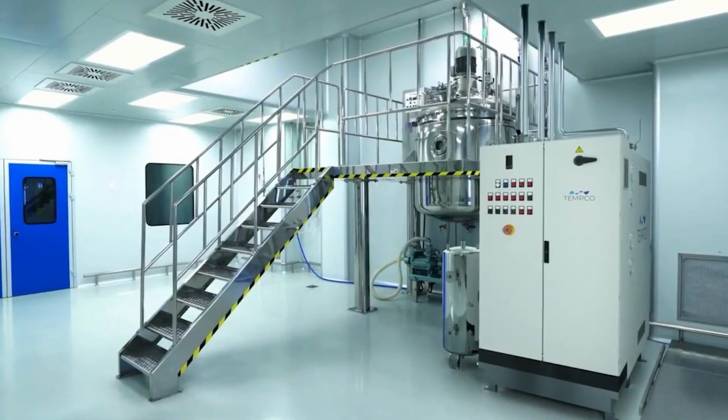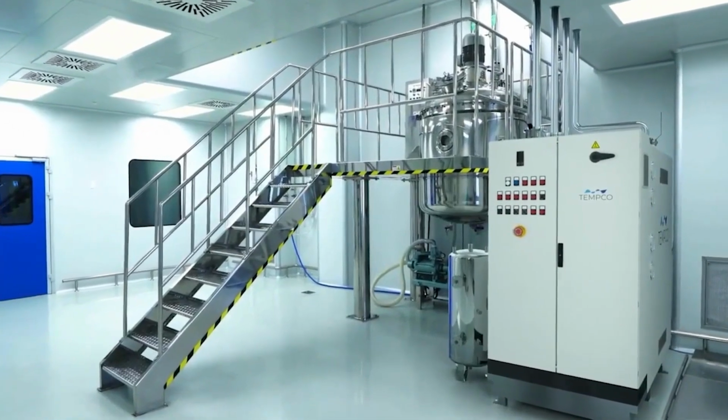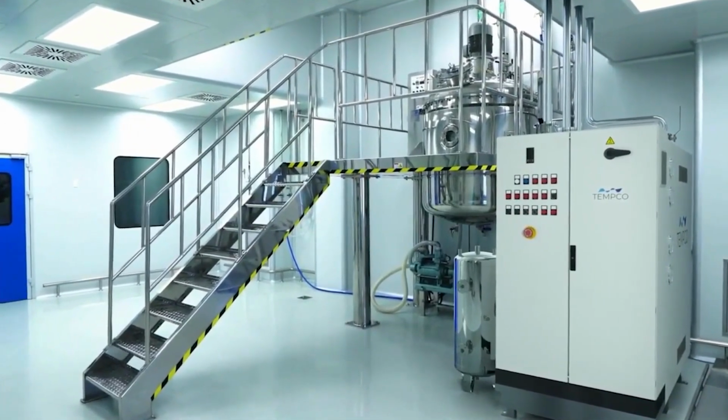Typically, we can use temperature control units with an atmospheric circuit or a pressurized circuit. The main difference is primarily the temperature range at which we operate with the unit. Up to 90 degrees, we can obviously use an atmospheric unit. Beyond 90°, due to obvious boiling issues, we must use pressurized water units, meaning with a closed, sealed circuit that withstands pressure, like a pressure cooker. Obviously with other types of safety measures, but this is a topic we might address at another time.